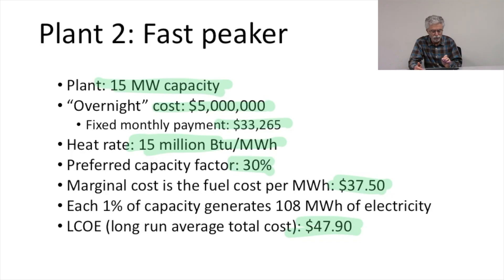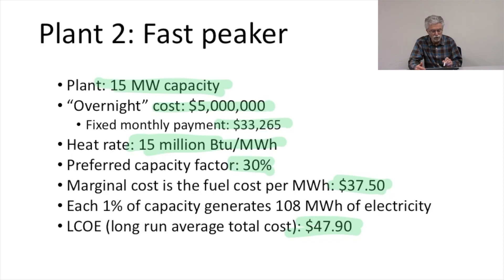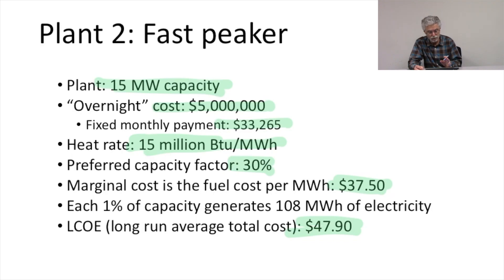It has a fixed monthly payment of $33,265 over the course of our 30-year loan. The heat rate is 15 million BTU per megawatt hour — just shy of twice the heat rate of our base load power plant. The anticipated average capacity factor is 30%. The marginal cost for this plant is the fuel cost, which is $37.50 per megawatt hour.